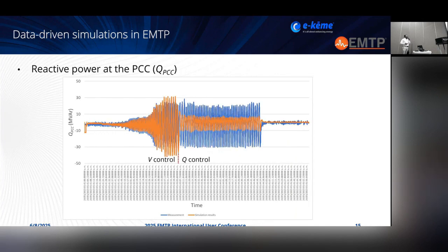In this slide, we can see the reactive power at the point of common coupling. And here's the interesting part. You can see in blue the reactive power oscillations that didn't dampen even when the control mode was changed. So we can see in simulation that the wind farm was capable of compensating these oscillations in the voltage control mode, and even more in the Q control mode.